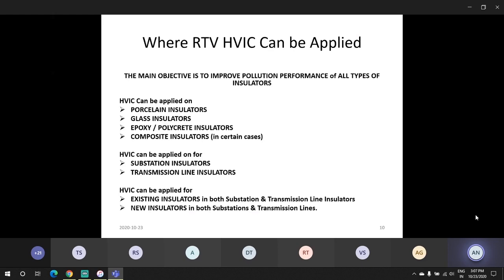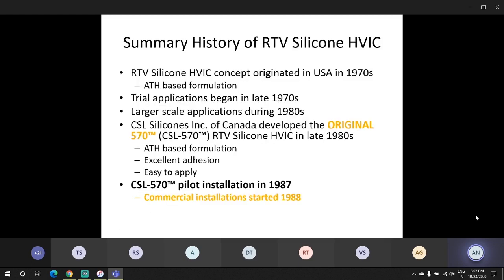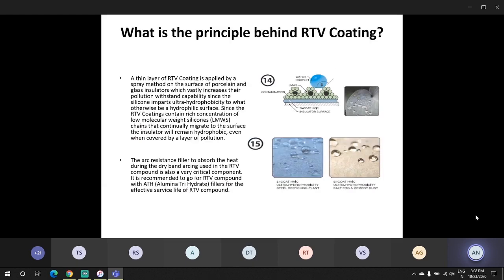The main objective of an RTV coating is to improve the pollution performance of all types of insulators: porcelain, glass, epoxy, polycrete, and composite insulators in certain cases. It can be applied on substation insulators. It can be applied on transmission line insulators. It also can be applied on existing insulators and new insulators for both substations and transmission lines. The history of RTV dates back to the 1970s. Dow Corning is the inventor of this technology. The trial applications started in the 1970s and large applications started in the 1980s. CSL Silicon developed our RTV HVIC in the late 80s, and the pilot installation was done in 1987, and commercial installation started from 1988.